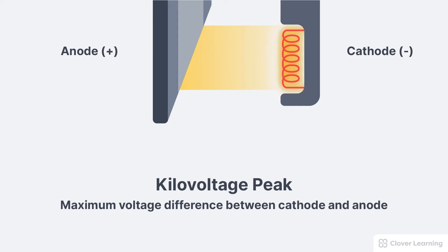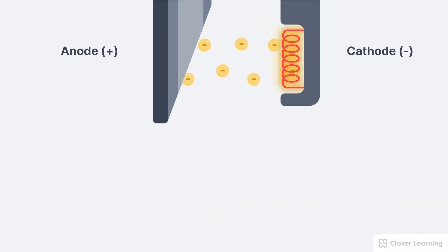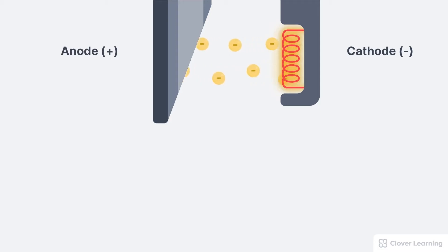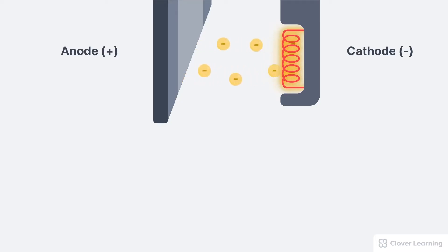The KVP describes the maximum voltage difference between the cathode and anode during the x-ray exposure. This voltage difference is very important because it is what forces the electrons to move across the x-ray tube. The electrons at the cathode are negatively charged and the anode is positively charged, so since opposites attract, the negatively charged electrons are drawn across the x-ray tube and collide with the positively charged anode. Without the kilovoltage applied to the x-ray tube, the electrons would not move and no x-ray production would take place.